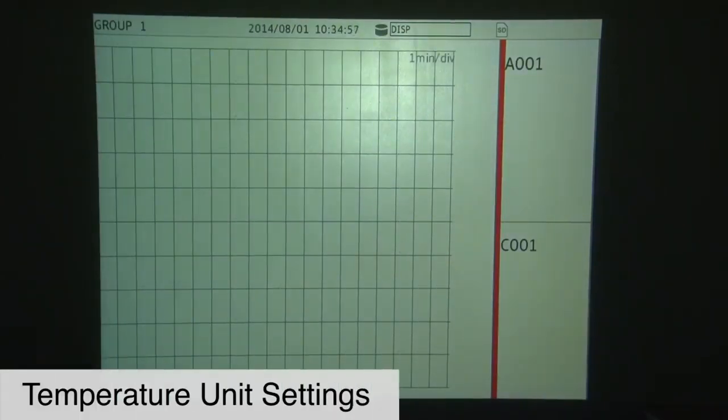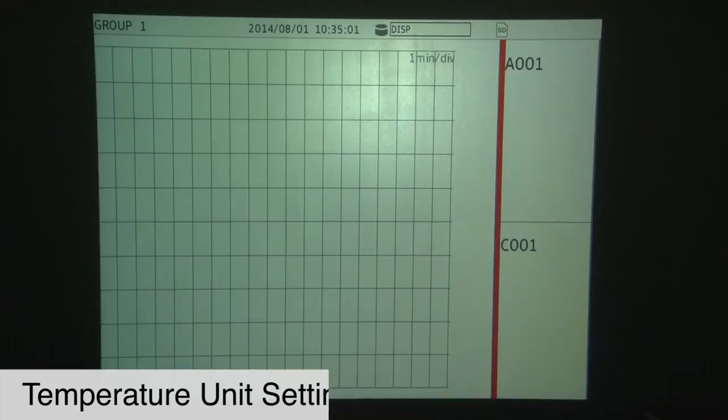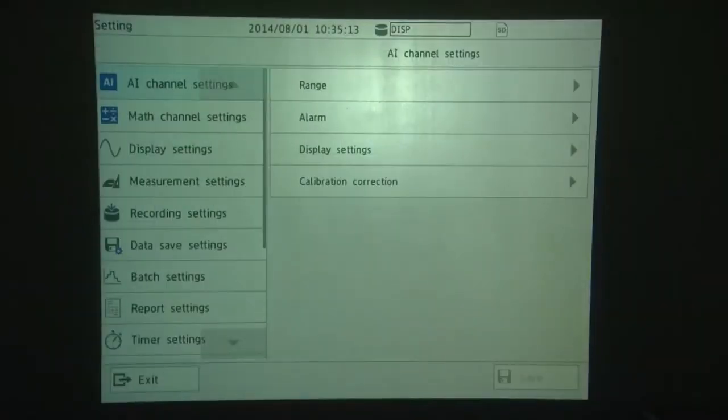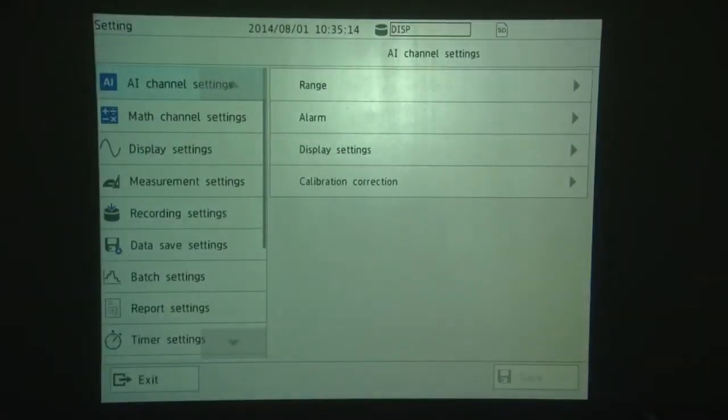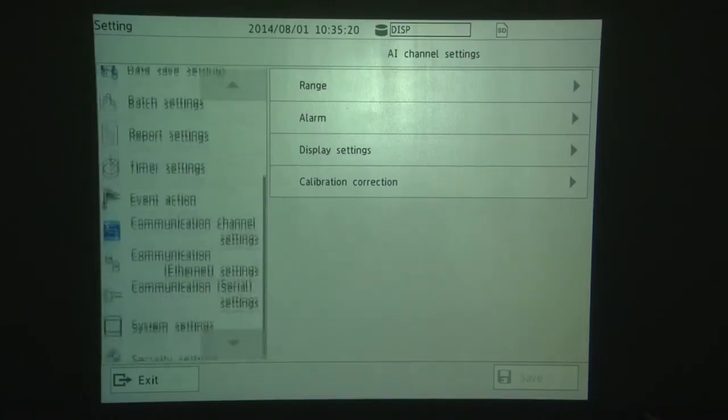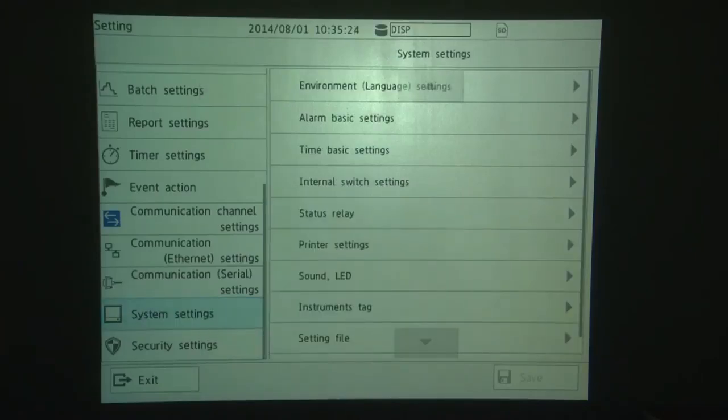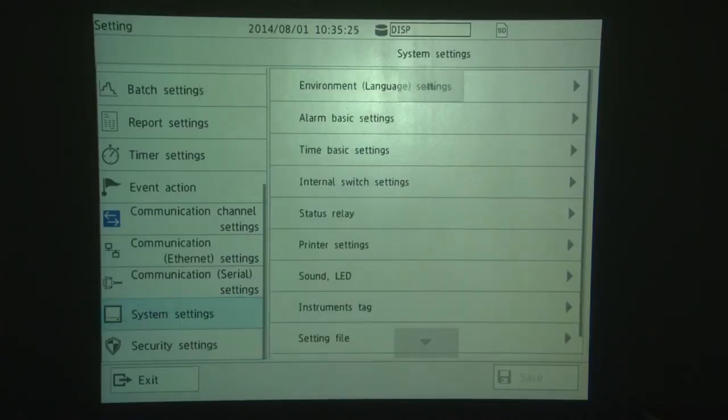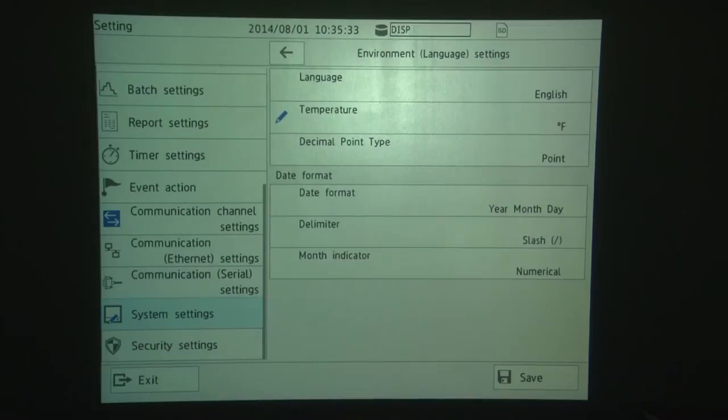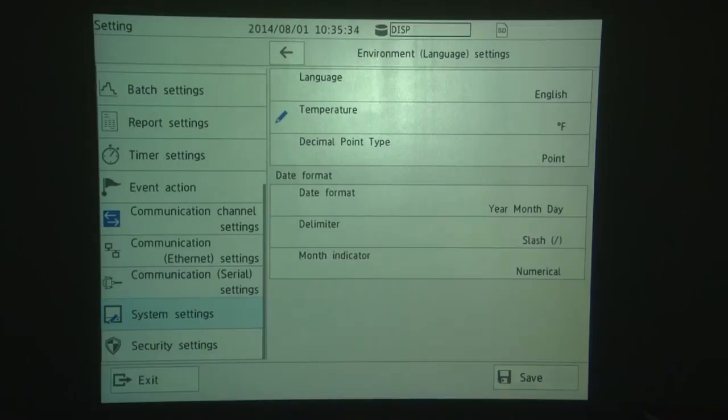Okay, the next thing we're going to take a look at is the temperature unit settings. For thermocouple and RTD measurements, the GX defaults the settings to degrees C. If you'd like to see temperature displayed in degrees F, hit the menu key, touch the setting menu, and you'll see the main setting menu directory on the left. Slide your finger up and go to System Settings. Choose Environment Language Settings. Go to Temperature. And then change the units from degrees C to degrees F. Touch F and then touch Save.